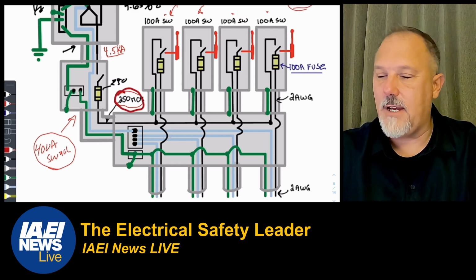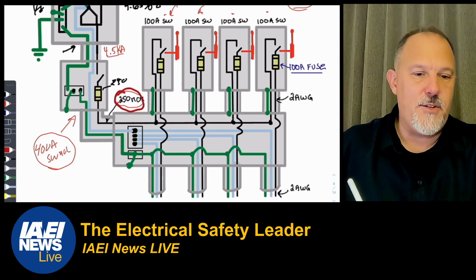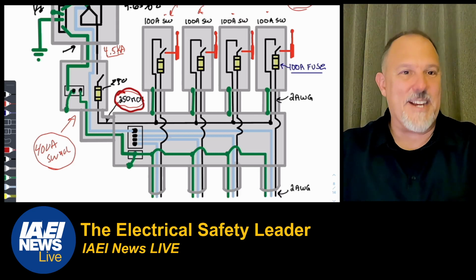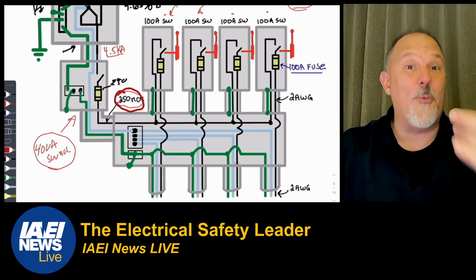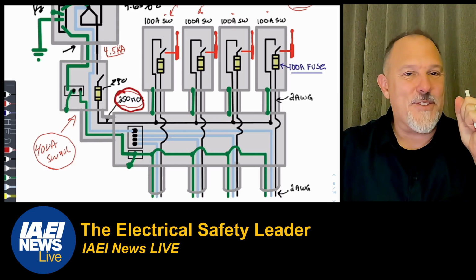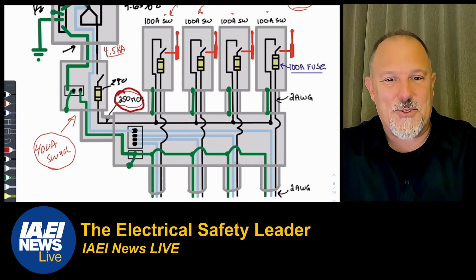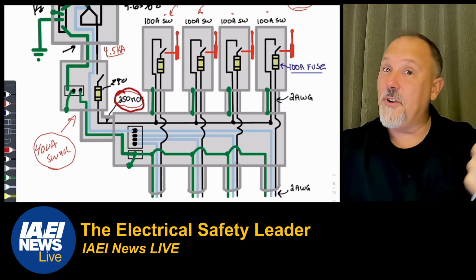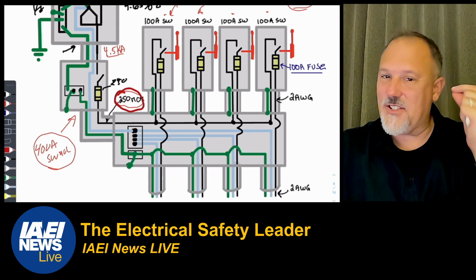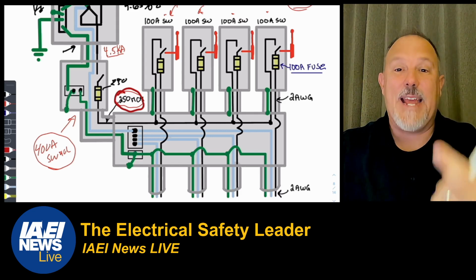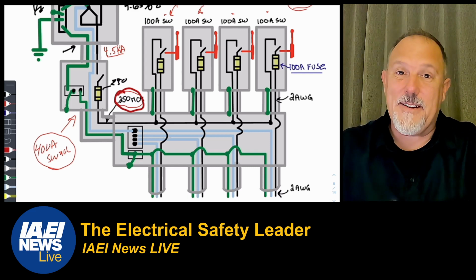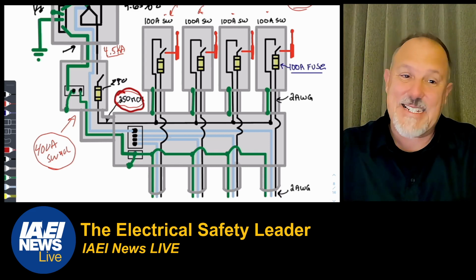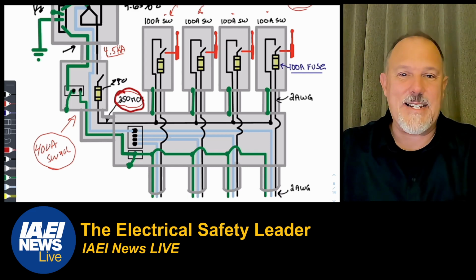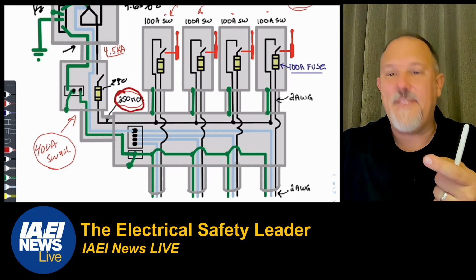And what's the ampacity of 250 MCM? What section do we go to in the National Electrical Code? What article do we go to first? So when you want to navigate the National Electrical Code, you've got to think, well, we know Chapter 3 is wiring methods and materials. We know it's Article 310 for conductors for general wiring, and then we know 310.16 is our ampacities, and we have our Table 310.16. So that's how we navigate to the right place.